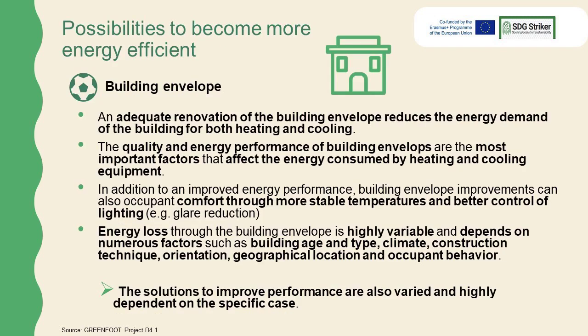Another possibility to become more energy efficient is in the field of building envelope. An adequate renovation of the building envelope reduces the energy demand of the building for both heating and cooling. The quality and energy performance of building envelopes are the most important factors that affect the energy consumed by heating and cooling equipment. In addition to an improved energy performance, building envelope improvements can also improve occupant comfort through more stable temperatures and better control of lighting, e.g.